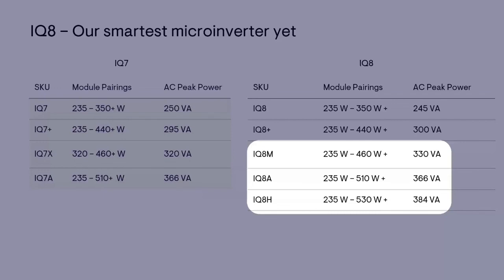Next question: if you have an existing M250 with IQ8 system, with battery and generator, do you need to load shed the M250s? Let me reiterate an earlier point - it's really important to understand that M250s can't be installed in the same microgrid with IQ8s. If you have a customer with M250s who wants to add IQ8s for a sunlight backup configuration, they'd have to replace the M250s with IQ8s. If you're also asking about a generator - if they want microinverters to be able to operate with the generator, they would have to upgrade them from the M250s.